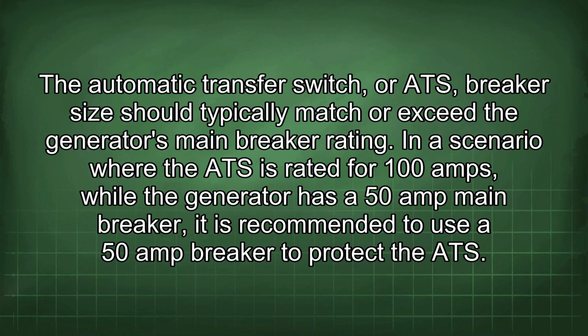The automatic transfer switch, or ATS breaker size should typically match or exceed the generator's main breaker rating. In a scenario where the ATS is rated for 100 amps while the generator has a 50 amp main breaker, it is recommended to use a 50 amp breaker to protect the ATS.